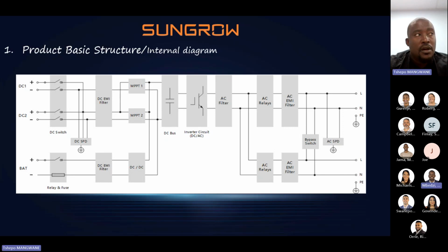Yes, you can limit on the grid tie system. Mainly, what are you talking about? Converting a hybrid system to a grid tie, or a straight grid tie system? Oh no, I just mean on this inverter, because you mentioned something about it going to overload if it exceeds, let's say, a kilowatt per phase. Unfortunately, the power active on this hybrid system cannot be set. But obviously, if you do an installation for a hybrid system, you will size according to the load. So it's hard to find the system tripping. If your panels are sufficient, it will provide the backup without batteries as well.